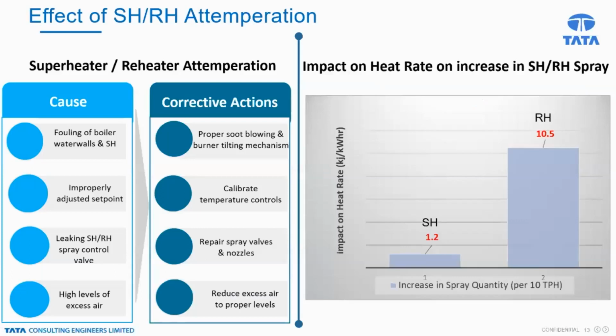The second one, talked about I think in the initial discussion also, is the spray water or attemperation water, both in the case of superheater and reheater. This also has direct relevance to the heat rate. Why is the superheater and reheater spray water quantity increasing? Because of fouling of boiler water walls and superheater surfaces, improperly adjusted set point, leakage in the spray water control valves, and higher levels of excess air. So these are the various causes due to which the spray quantity would increase.